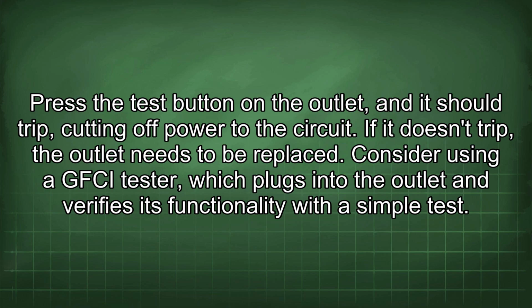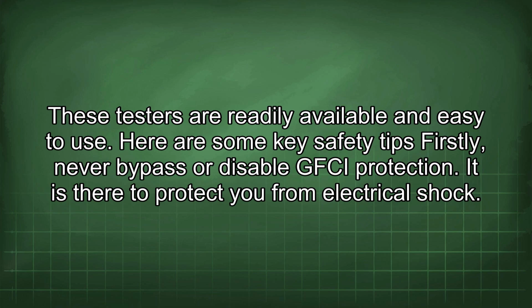Consider using a GFCI tester, which plugs into the outlet and verifies its functionality with a simple test. These testers are readily available and easy to use. Here are some key safety tips. Firstly, never bypass or disable GFCI protection. It is there to protect you from electrical shock.